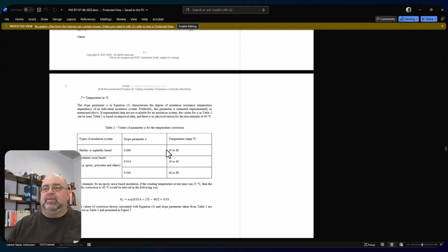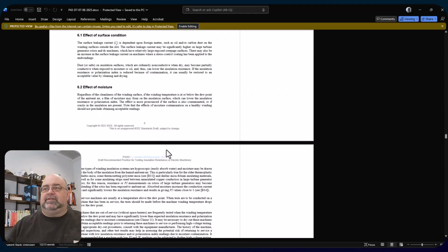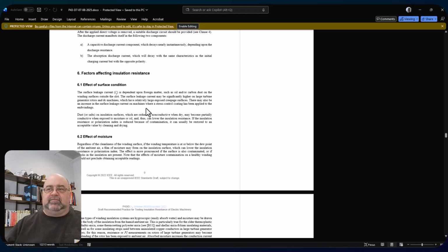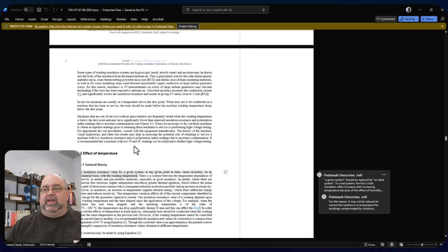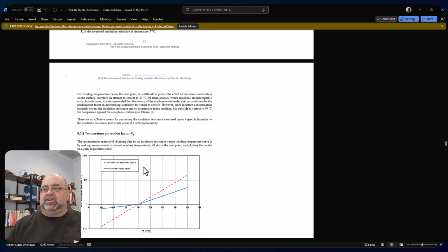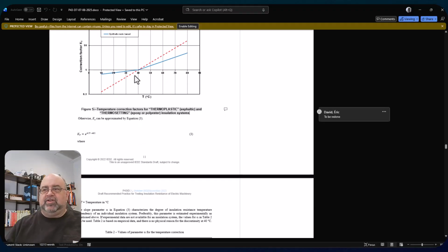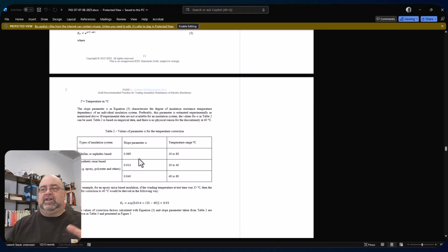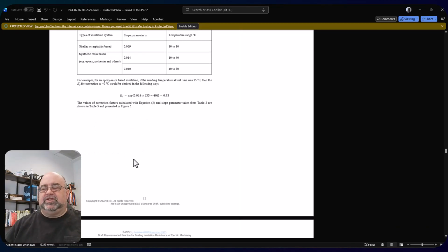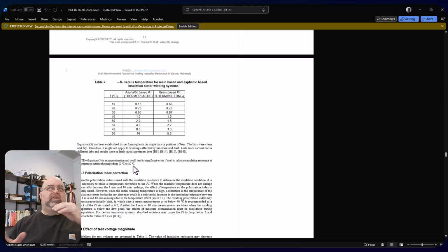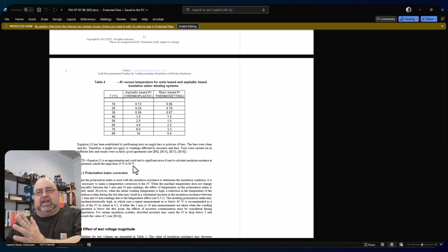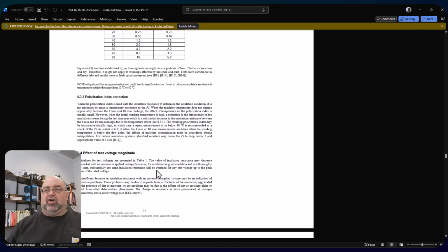I did. Impact of temperature. Yeah, here we go. That's what I was looking for. Surface condition. Okay, so contamination, oil, carbon dust, etc. Effect of moisture, effects of temperature. Now, I don't believe we included in this how to correct for temperature. So you notice this here. There's different types of changes based upon the type of material being used. Tends to happen, you tend to have to correct at 40 degrees centigrade and higher. So if you are testing a cold winding, that's better because then it's an easy doubling for every 10 degrees centigrade or halving type calculation. So calculations are all here.